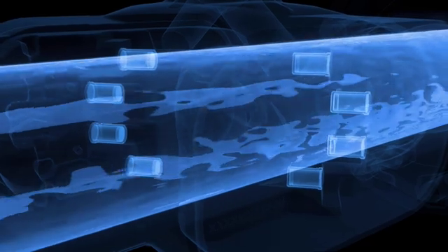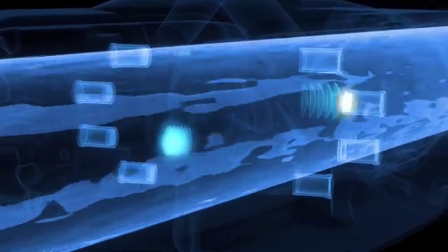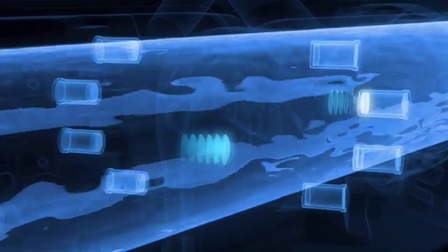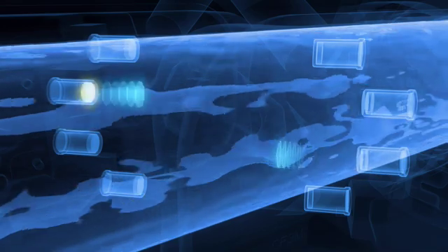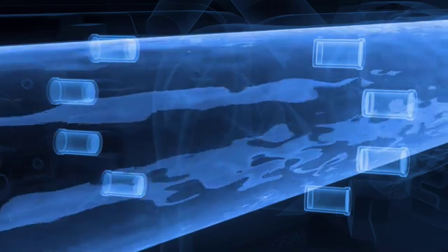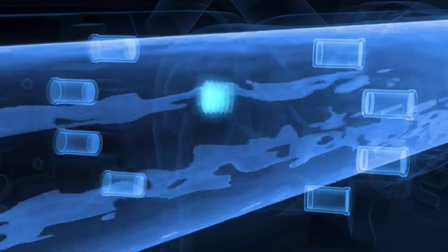Once the fluid starts to flow in the measuring tube, the ultrasonic signals are accelerated in the direction of the flow and decelerated against the flow. As a result, the ultrasonic signals now have different transit times.